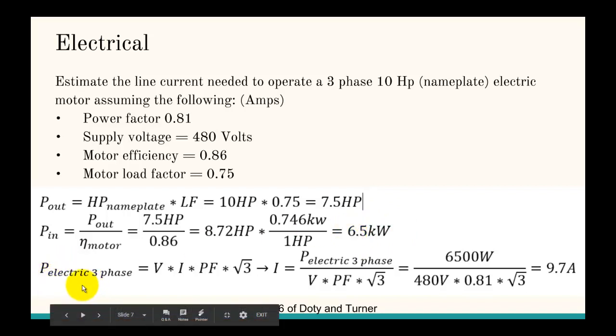So, and then, we take the equation for three-phase electricity, which is the volts times the amps times the power factor times the square root of three. We solve for the amps, and then, in this case, the power has to be in watts. So, we divide the watts by the volts by the power factor and by the root three, and we get 9.7 amps.